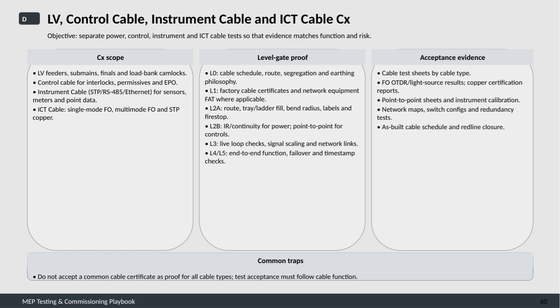L0 focuses on documentation, such as cable schedules, routing plans, segregation, and earthing philosophies. At L1, we verify factory cable certifications and conduct factory acceptance tests of network equipment, where applicable. L2A inspects physical installation aspects, including routes, tray or ladder fill, bend radius, labeling, and fire stopping.